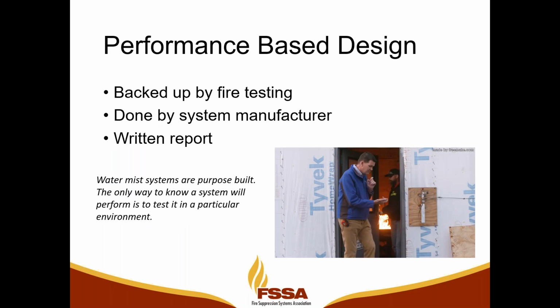And as Jonathan said, when we do performance-based design, we're going to mock up an enclosure to mimic your specific hazard, and we are going to test our system and find those design parameters that are most effective for that particular arrangement of things that you will find in your hazard, and we're going to generate a test report. And that test report is something that the OEM and the buyer of the system are going to stand behind and use to satisfy the local authorities that need to approve that system. And just want to stress again, unlike a sprinkler system, that we use a totally different design principle.